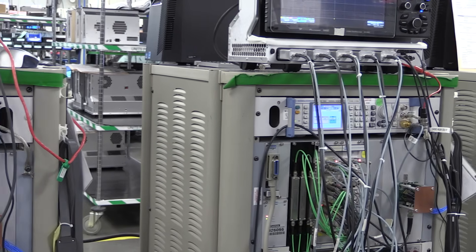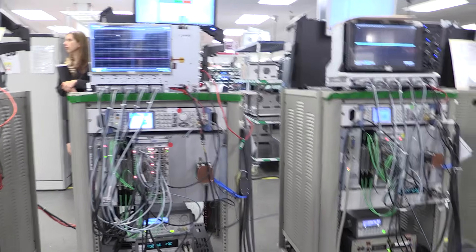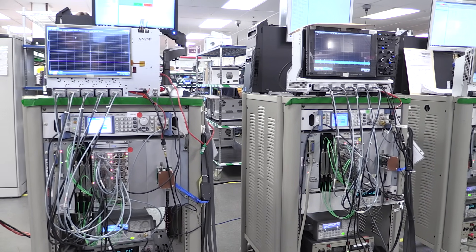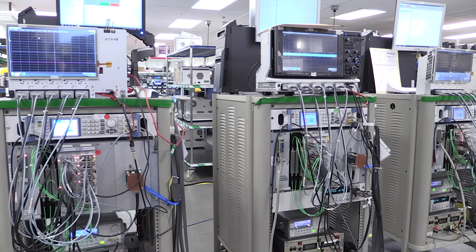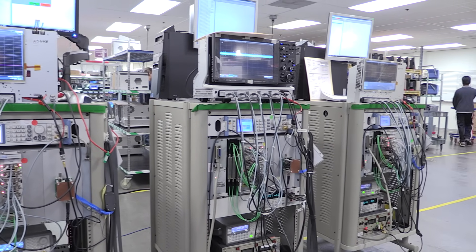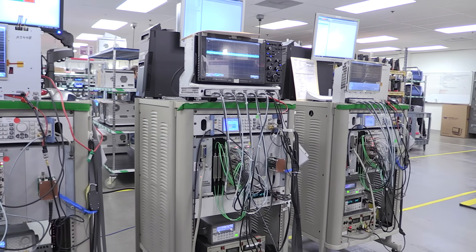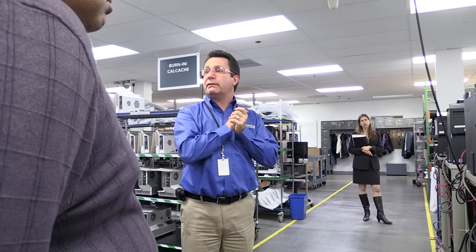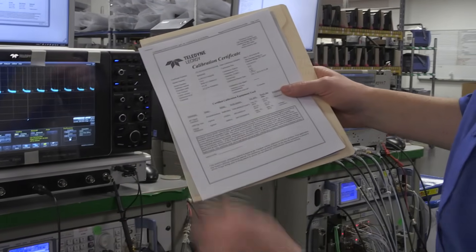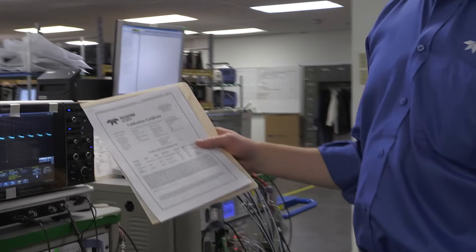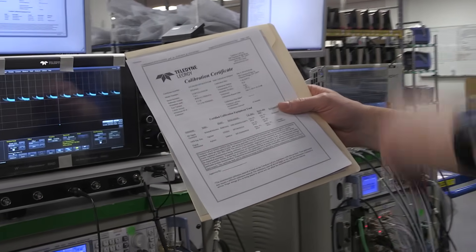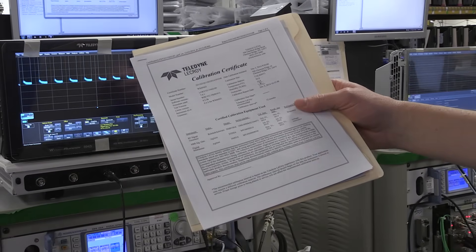If the output doesn't match the input, there are software adjustments the system will automatically make. Then using a precision Pickering switch box, we switch that signal to channel two, bring it in, digitize it, store it, read it out, make sure it works — one, two, three, four — change the volts per division, change the time base, run it again. There are thousands of measurements going on here. This is our performance verification — guaranteeing we're within spec, say 10 millivolts plus or minus one percent. The result of that test process, with all data about which signal generator was used and calibration dates, is fully traceable back to calibrated standards.